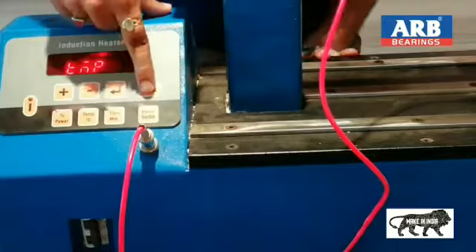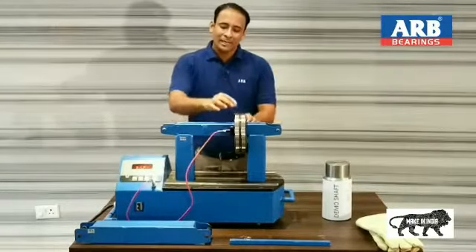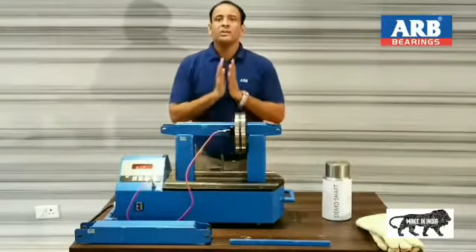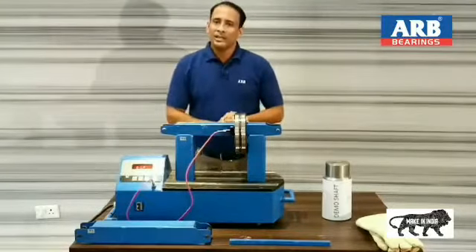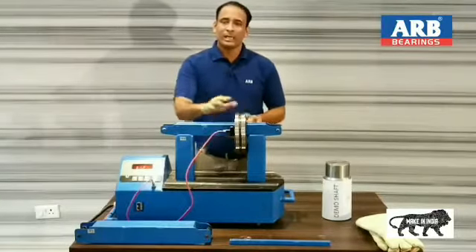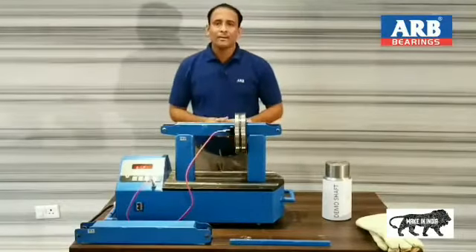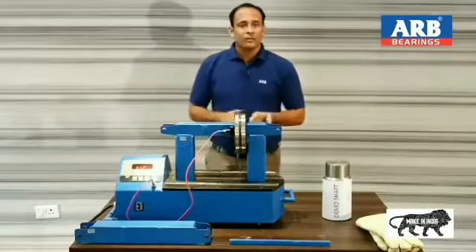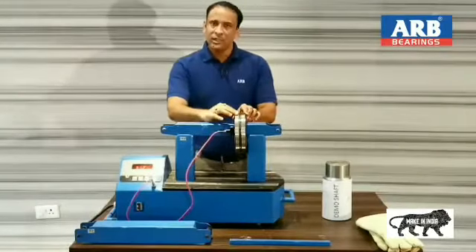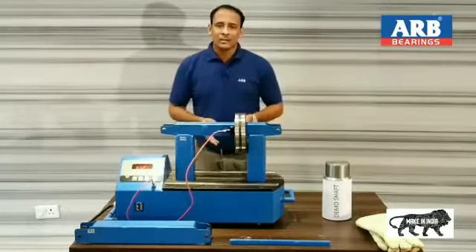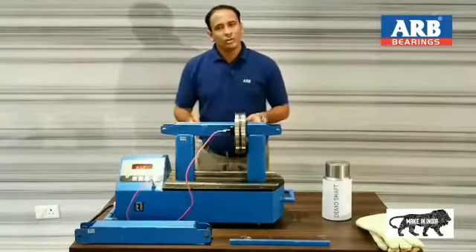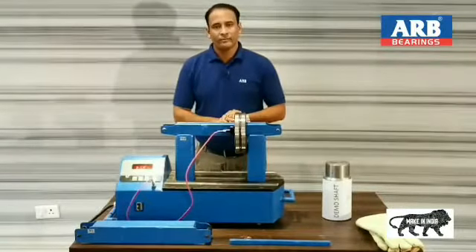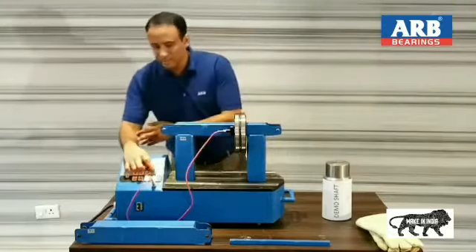Now I will press the cycle button, but before that I want to tell you that after completing this cycle the machine will automatically switch off after demagnetizing this bearing. At the end of the cycle you will hear a beep sound from the machine that will indicate that this bearing is being demagnetized. Demagnetization is a very special feature of the ARB make bearing induction heater, as if the bearing is not demagnetized then the bearing will attract metal particles during operation or during handling that may cause loss of bearing life. So here I will start the cycle button.